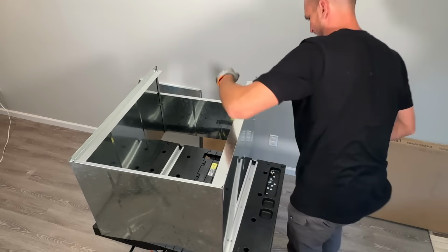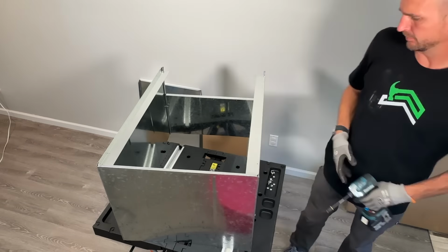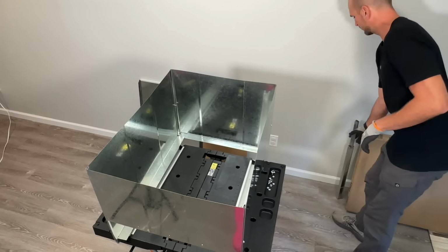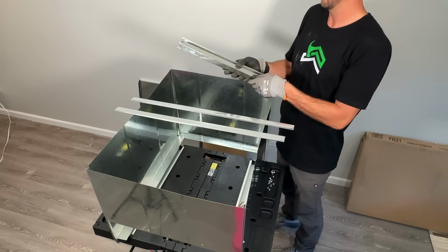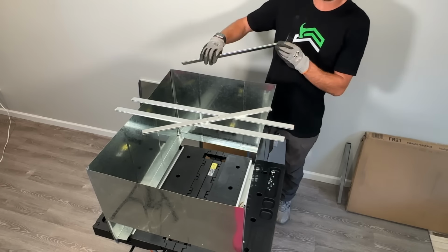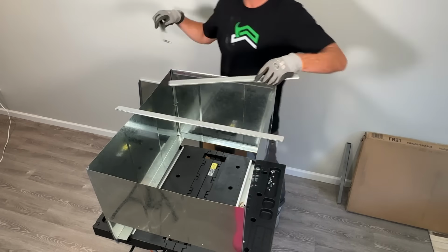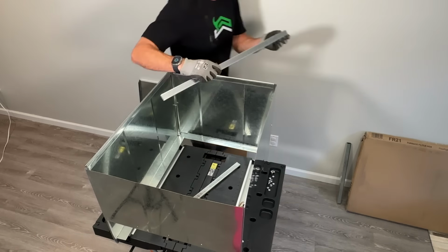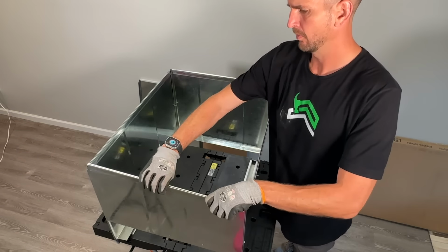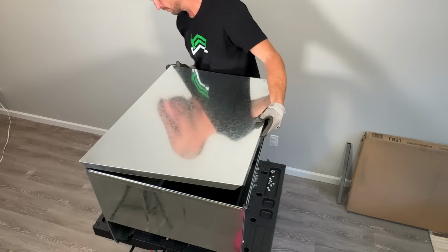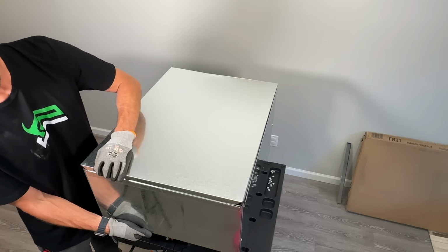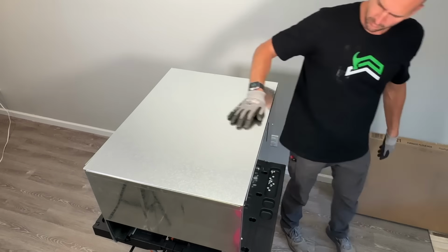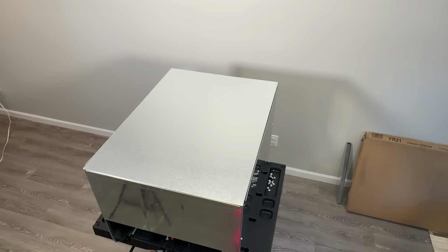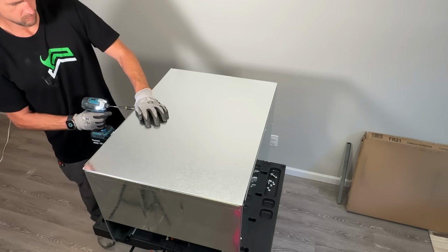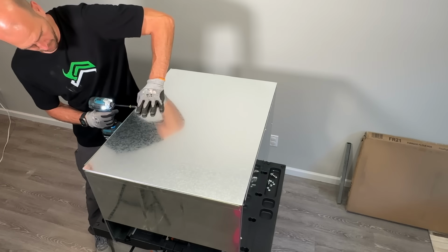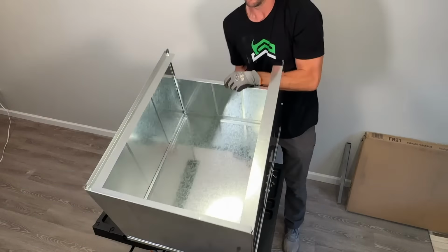Make sure you have those driven all the way in. Sometimes if you don't drive them far enough, it'll actually just push one side of the sheet metal as opposed to actually pulling those together. Now we have our S cleats. I'll put it on the back, the side, the other side, and the front, making sure the opening is pointed to the outside. So now when we put this bottom piece on, everything lines up, and we're able to secure that with 2 sheet metal screws, one on each side.